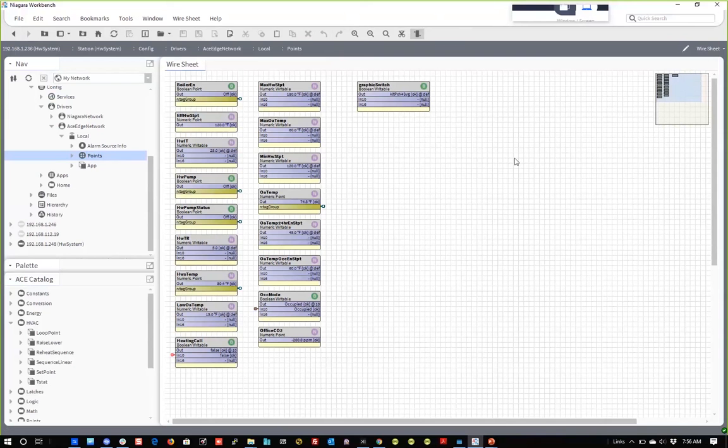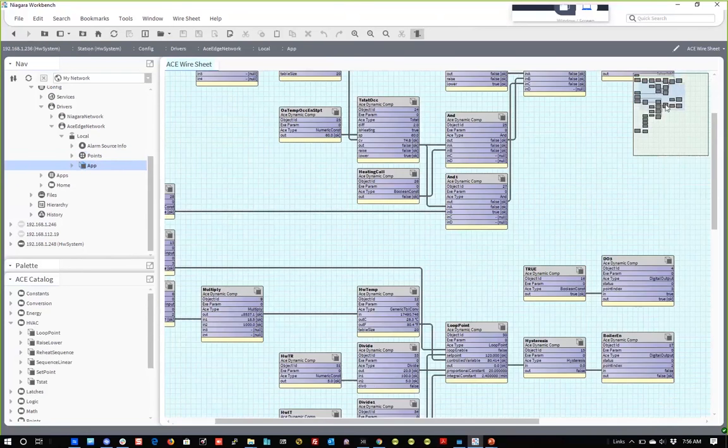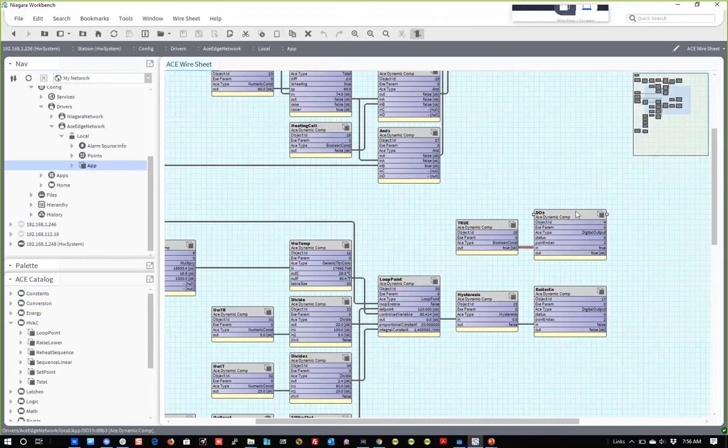Yeah, it all depends. What's the startup time? I've timed it at 12 seconds. What I did with my application, I just have a digital output go true when the application's running. The Edge 10 has 4 digital outputs, with an LED on the face of the controller. So I was just timing to when that LED turns on, meaning it completed its first cycle of the application. And it was 11 to 12 seconds.